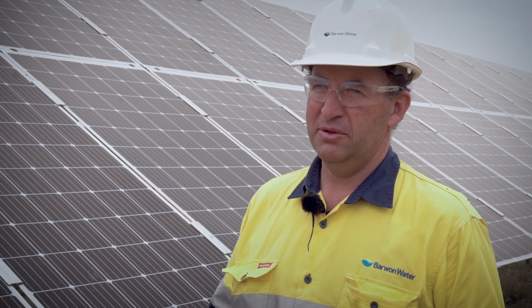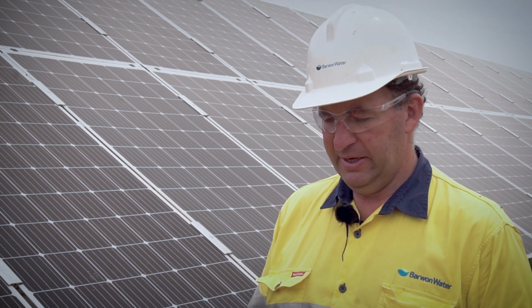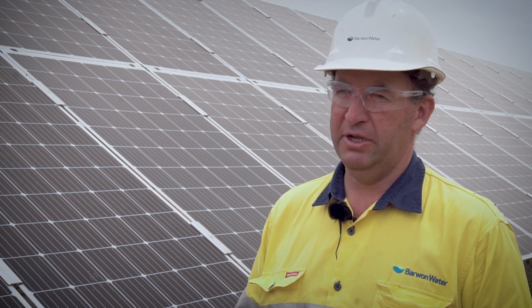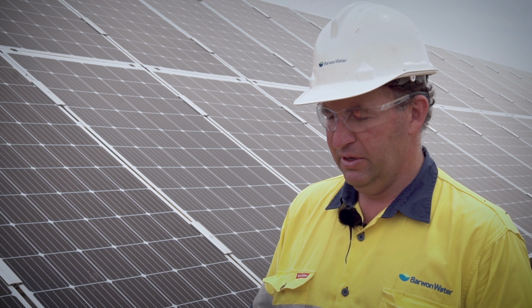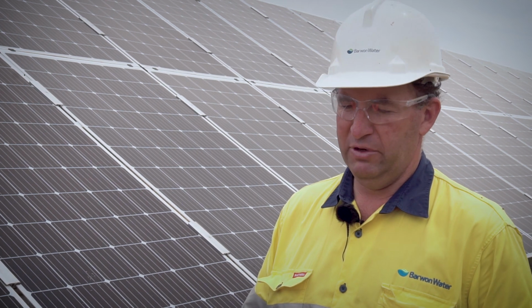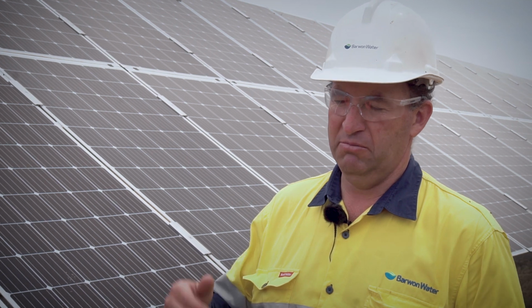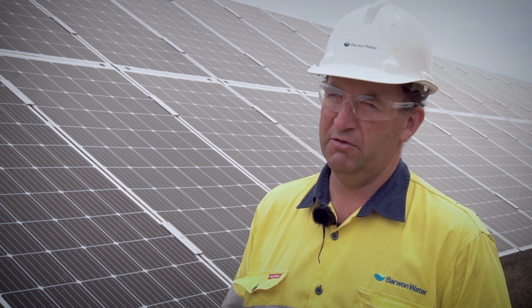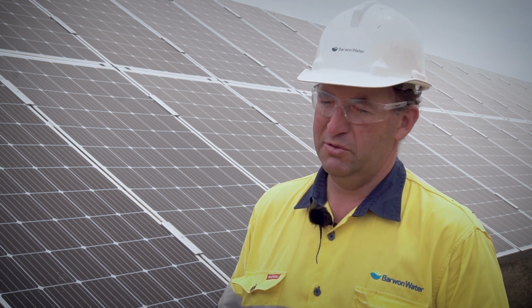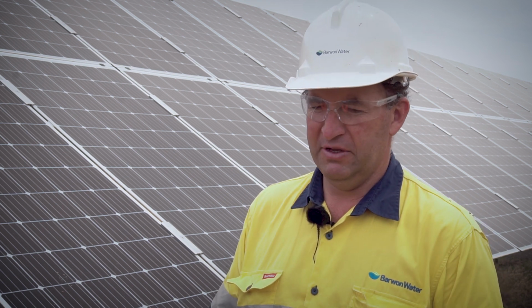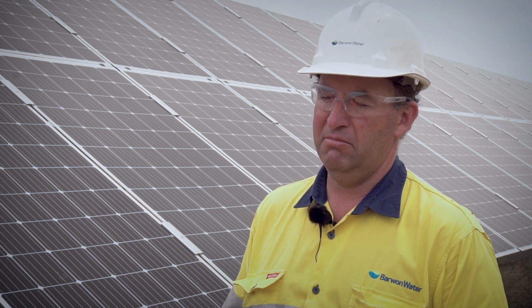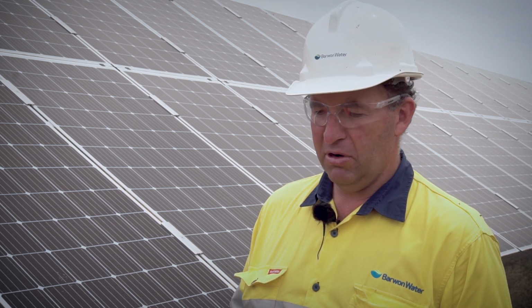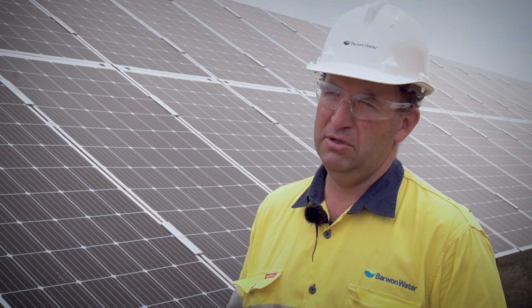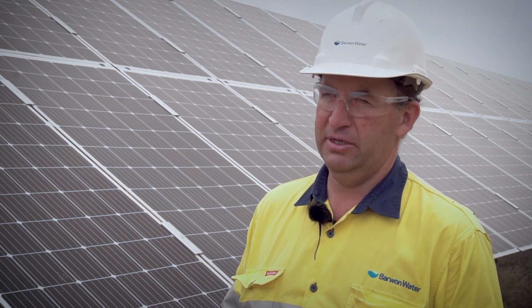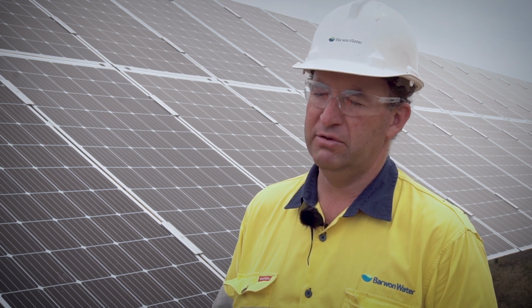We're looking to put some bird spikes on the top leading edge of the top panel. Ground selection where you're going to put your piles in has a bearing on meeting supply obligations. We have 2 sites within our arrays - we've got partial clay where we can ram the piles in, going 1.5 metres into the ground. Unfortunately we do have some rock in those paddocks, so we've done initial geotech studies to map where those areas are. Then to pile, we're primarily augering out the hole to drill and then ramming the pile in and stave sanding around that void cavity - about 30 seconds per pile to ram those in.